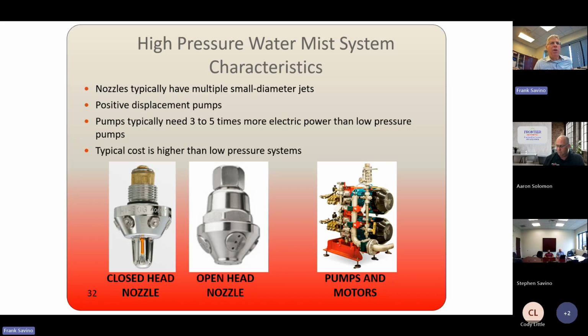Normally with a high pressure water mist system, you need what's called a positive displacement pump. That's depicted all the way to the right. And they usually require quite a lot of power compared to a low pressure water mist system, 3 to 5 times more power. And the cost for a high pressure is typically higher. And what I found is really there's not much of a benefit to high pressure because the water densities are about the same as low pressure. So I don't really see much of an advantage. What you see in the middle here is an open nozzle that you would use, say, for a machinery space, like an emergency generator.